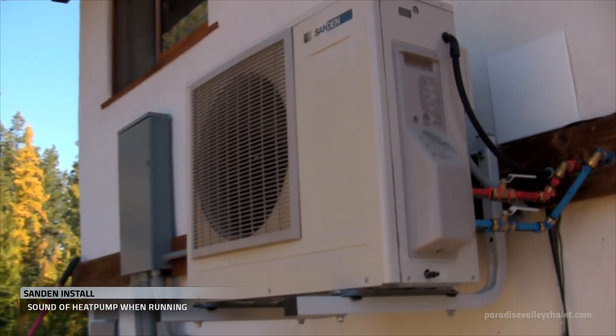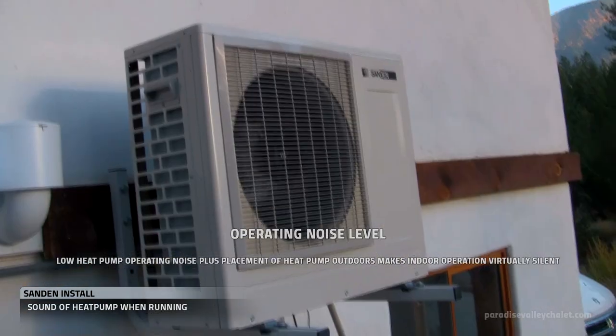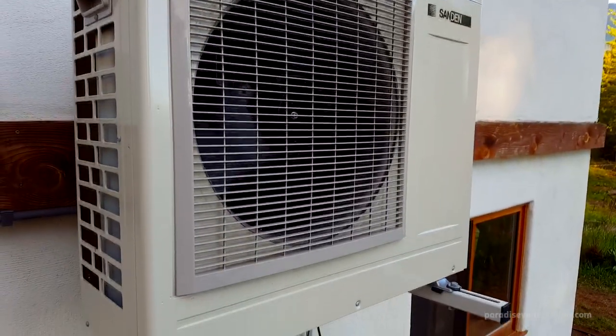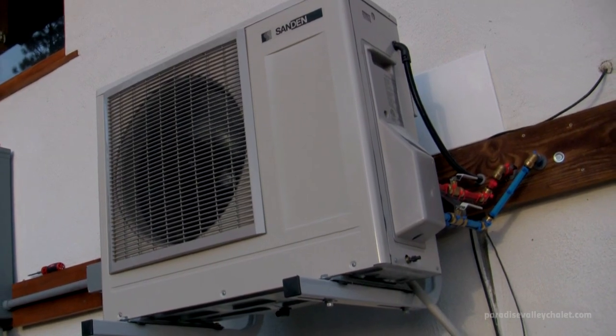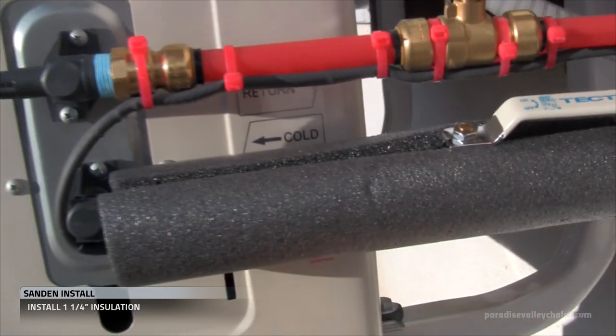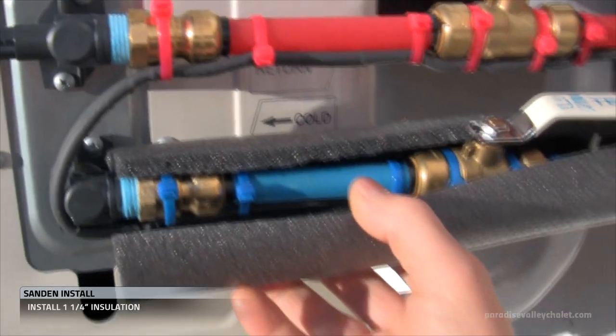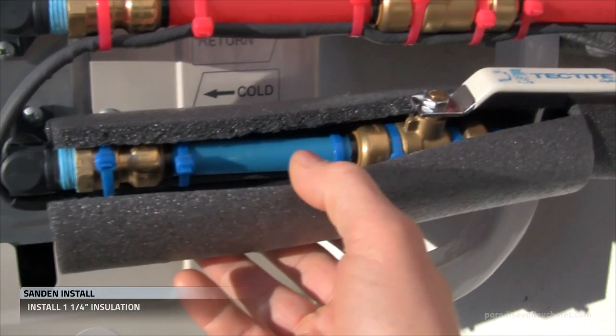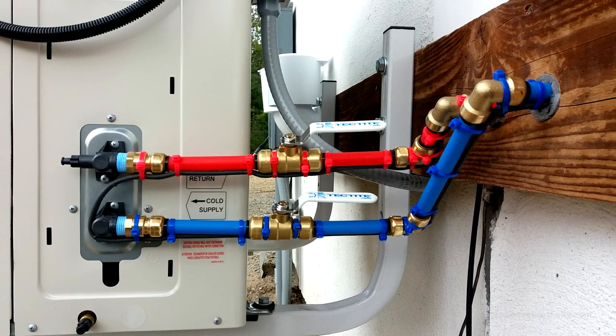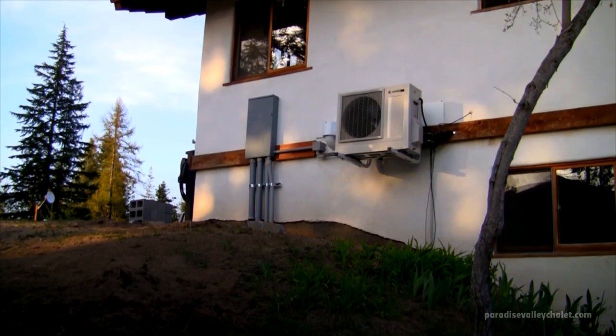Now that the system is running, let's check out the sound of the Sanden. It is whisper quiet, and most of the time the heat pump is off — it only turns on when the hot water in the storage tank is drawn down. We've been watching the system for a few days and there are no leaks. This one-and-one-quarter inch insulation will account for the plumbing, strap ties, and heat tape, and we'll install it from the heat pump to where the plumbing enters the building. Just in time for winter, the Sanden performed outstanding throughout the winter season.